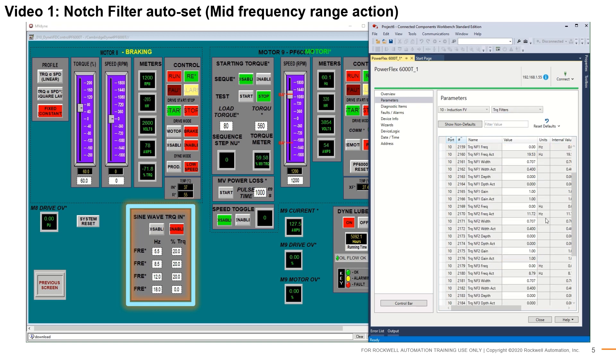Now all four notch filters are set. Removing the harmonic content that initially set the filter does not reset it. This allows the filters to respond immediately to subsequent characteristic resonance events should they occur.